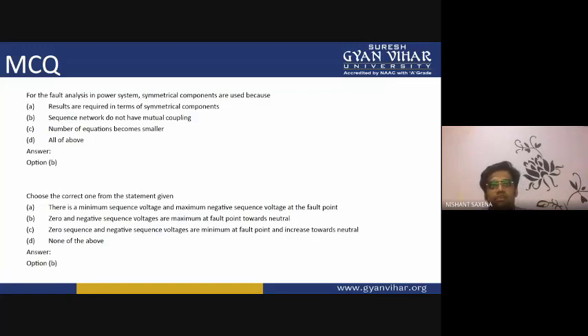And the last question: choose the correct one from the statements given. There is a minimum positive sequence voltage and maximum negative sequence voltages at the fault point. No, it is not right. Why? You cannot say that negative sequence voltages are always the maximum. Second, look at option C: zero sequence and negative sequence voltages are minimum at a fault point and increase towards the neutral. No, it is also wrong. It doesn't increase towards the neutral. The option left is option B, that zero and negative sequence voltages are maximum at the fault point and decrease towards the neutral.